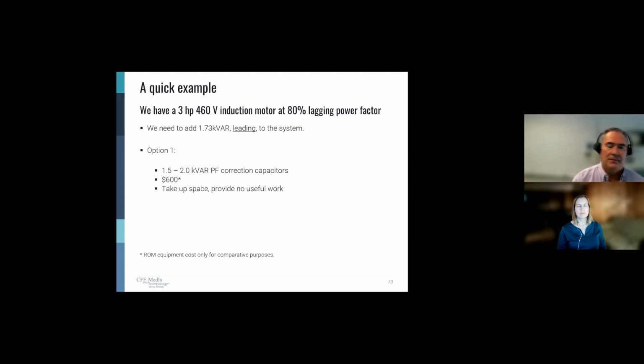So we got some options. One is we can add just simply some power factor correction capacitors. It's a gray box, hangs on the wall. In this case, it's not going to be very big. You wire it into the system and it corrects the power factor. Again, rough order of magnitude of the component only is about $600. I didn't try to figure out how much it would cost you to wire it or install it, and so forth. And like we said, it hangs on the wall, it takes up space and provides no useful work other than it corrects our power factor.